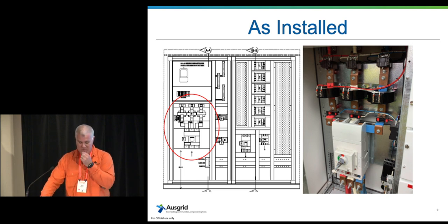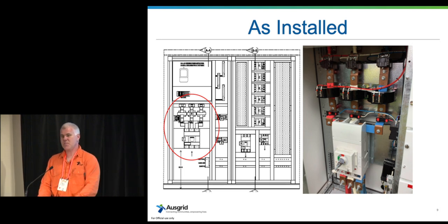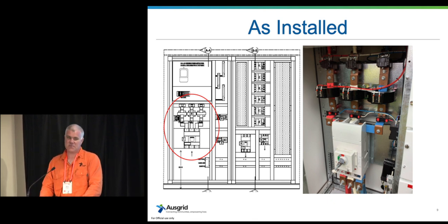As Max was pointing out before about Annex ZD, keep in mind that the New South Wales Service Rules does require a ZC test to be done as well. That is a special test, which effectively means ZD. So we are looking for that containment within the SPDs.